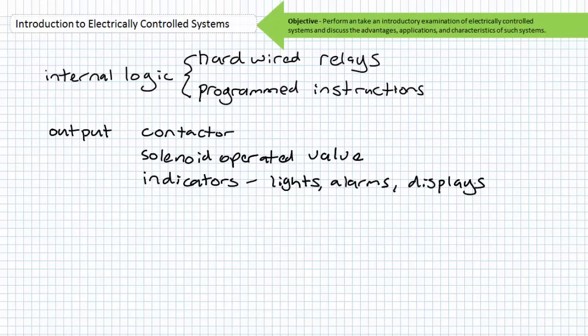Other output devices exist, such as pilot lights, displays, alarms, or buzzers, which can be considered forms of indicators that simply tell human operators what condition the system is in. Indicators typically only interact with the control level voltage. However, this isn't always the case. Outputs can again be thought of as the hands and feet of an electrically controlled system, those parts that perform physical labor or announce status to the outside world.